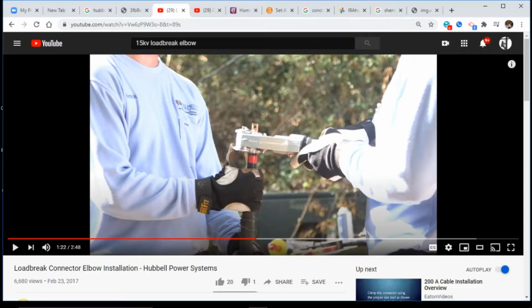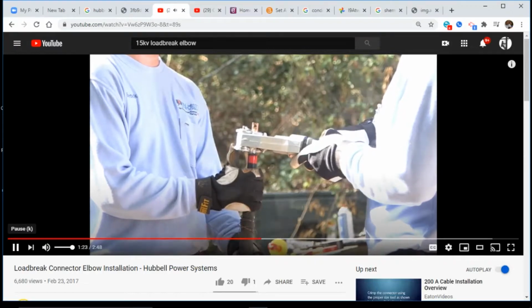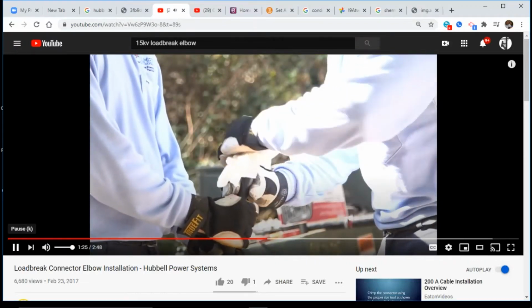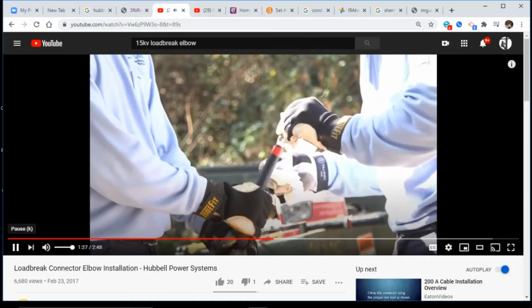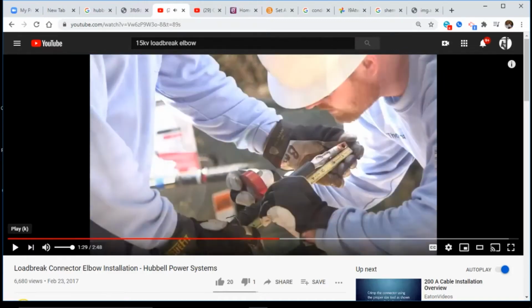If you crimp from bottom to top, it's going to leave a bubble in it where that aluminum couldn't escape anymore, and you're going to have extreme difficulties pushing the elbow on. The elbow fits rather tightly. Successive crimps to prevent bowing. Wipe excess inhibitor at the base of the lug and smooth any sharp edges on the crimps of the lug.